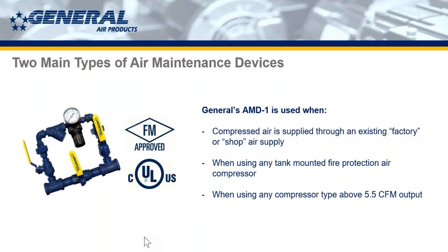So you don't have the full capability of a compressor trying to keep up with the air loss associated with the head going off. So compressed air is supplied through an existing factory or shop air supply when using any tank-mounted fire protection air compressor. So any tank-mounted compressor is going to require an air maintenance device. And then when using any compressor above 5.5 CFM. We'll go over this information multiple times in multiple ways, because it's often confusing the way it's put in the standard. The wording is a little tricky. But really, the way it reads is if you're above 5.5 CFM required for filling your sprinkler system in 30 minutes, you should be in a tank-mounted unit anyway, in which case you need an AMD1.